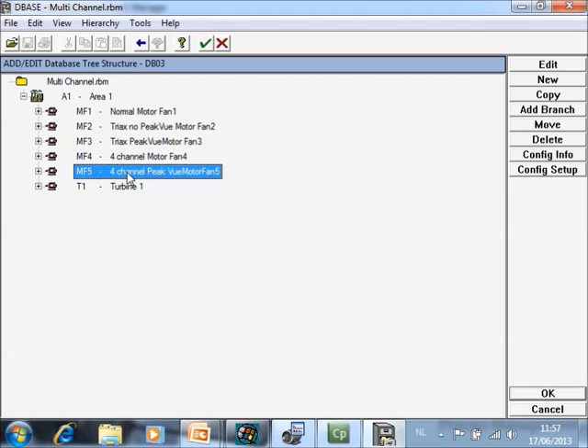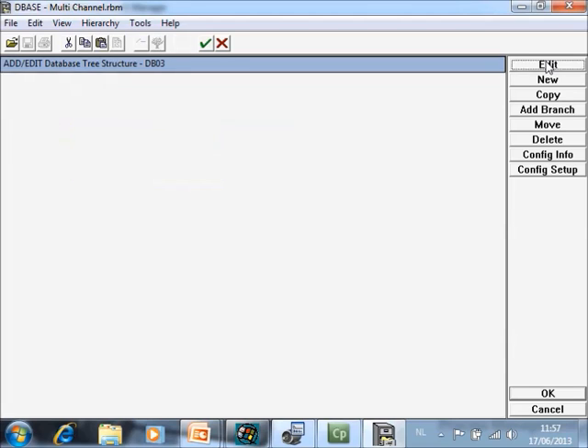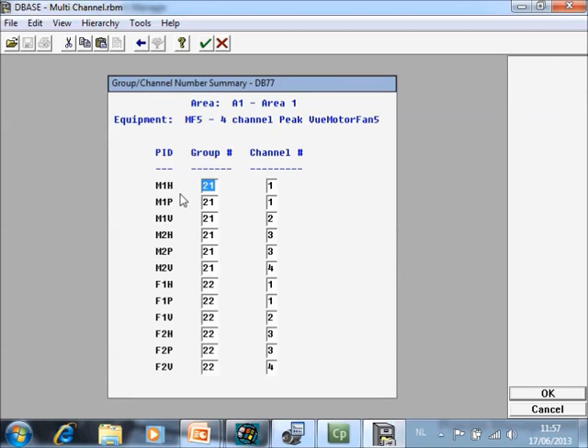If you also want to add PeakVue measurements on top of that, you can do something special. Now I have six points in the same group. The data collector is four channels, so what will happen is it will collect four of those six points simultaneously and then automatically in a sequence collect the two additional measurements. However, if you configure more than four, it will measure them with only one acquisition start, creating an illusion that it is taking six measurements simultaneously.